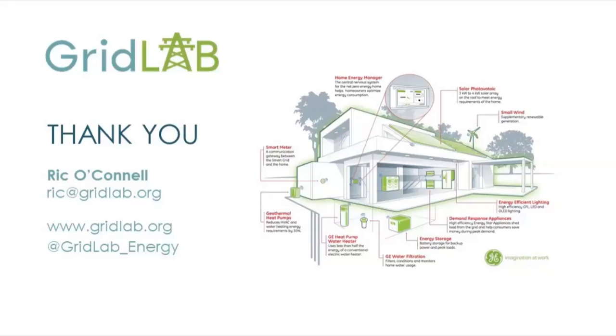Mark goes on to say that the use of volt watt is helpful to ramp down output just before the system would trip anyway. I think those are two excellent points, so thank you, Mark, for bringing that up, because I should have brought that up when I gave the presentation. I should have been clear that the 0.5% curtailment that we saw from volt var was a worst case, as Mark makes a very good point. That's in a very heavily loaded Hawaiian system with a lot of generation compared to load. And Mark's point is that if those systems were legacy systems at unity, they probably would have just tripped off.